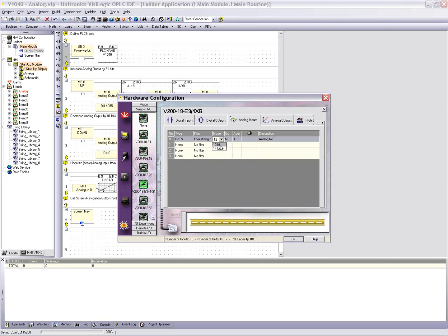You can see I have it on 12-bit scaling mode. On some of the controllers and snap-ons, it allows you to switch between 12 or 14-bit. Why would you want to use one over the other? The 12-bit is going to be a faster calculation, but it's also less accurate. If you have 14-bit resolution, your max bit value is 16,383 versus 4,095 with 12-bit. So 12-bit is a faster calculation, faster input response, but the 14-bit would be a more accurate value for your sensor.